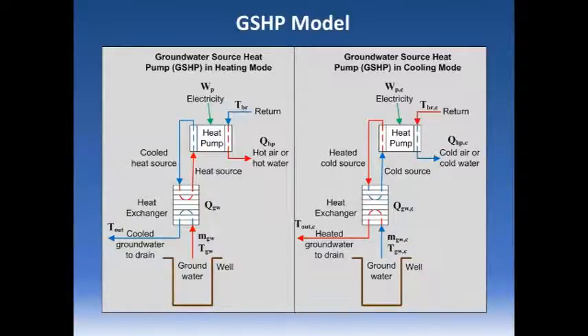If you use a higher flow rate, therefore a lower delta T, you will probably have less scaling because there's less driving force, and the water is in the heat exchanger for a shorter time. One of the assumptions I made about the amount of scale buildup had to do with kinetics, so I think both cutting down on delta T and cutting down on residence time will reduce scale formation.